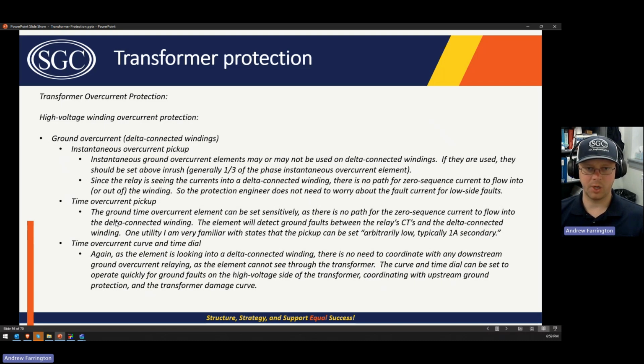There's little to no risk of it misoperating, because the delta winding doesn't allow any zero sequence fault current to pass through it, so you're not worried about through faults. So the area of exposure is really only between the CTs and the transformer winding. And so especially if the CTs that are feeding your relay are within the bushing of the transformer, there is basically no area for there to be a fault that isn't within the transformer. So you can set that low and fast, and that's what we're talking about for the time over current pickup here. The client I'm most familiar with sets their ground time over current pickup to something that's arbitrarily low, like 1 amp secondary, and then just sets it low and fast, and there's little to no risk of it misoperating.